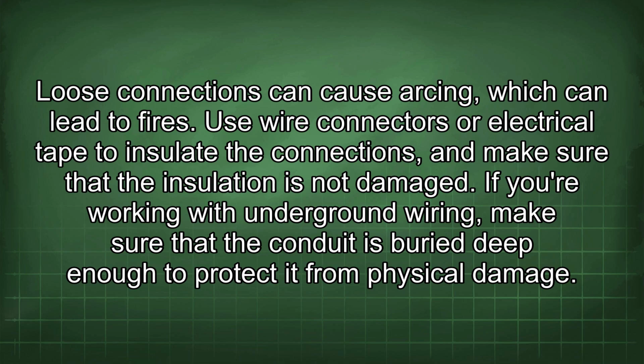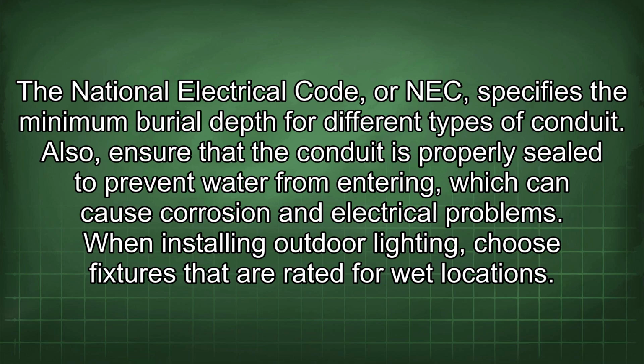If you're working with underground wiring, make sure that the conduit is buried deep enough to protect it from physical damage. The National Electrical Code, or NEC, specifies the minimum burial depth for different types of conduit. Also, ensure that the conduit is properly sealed to prevent water from entering, which can cause corrosion and electrical problems.